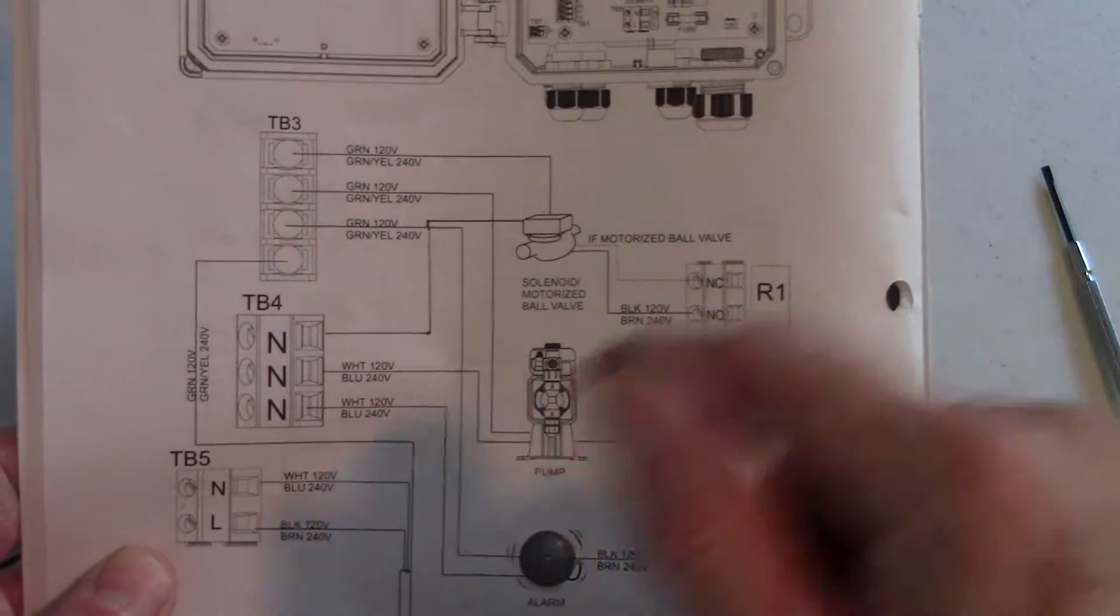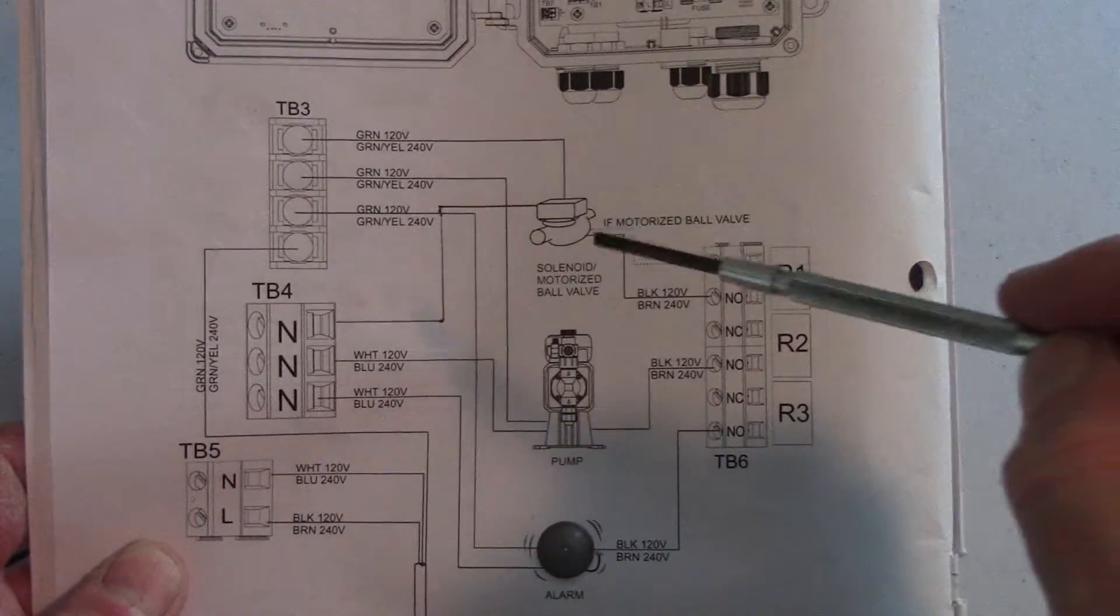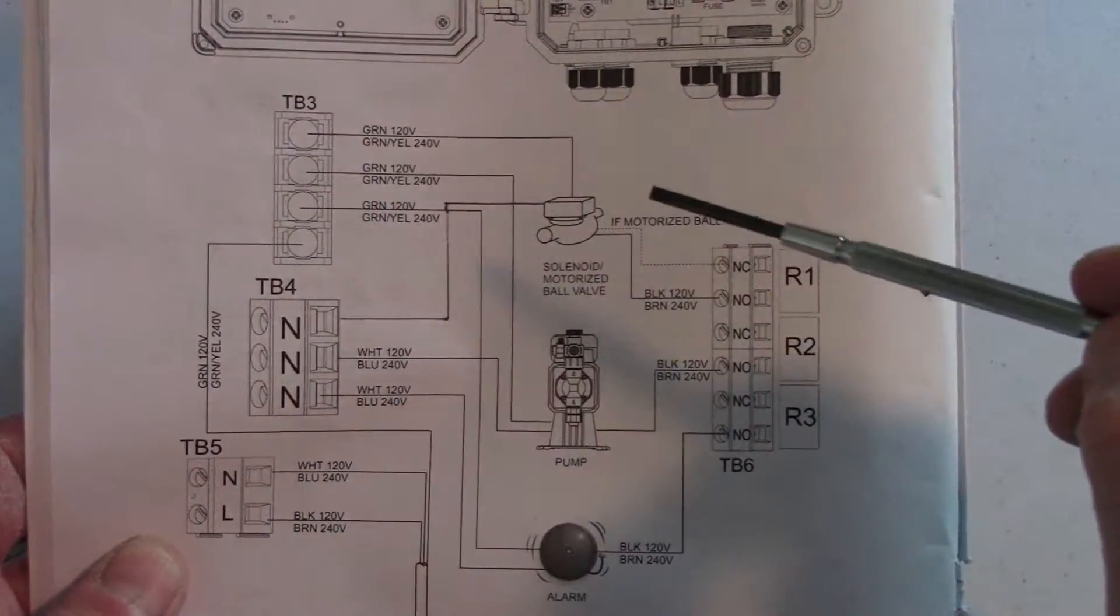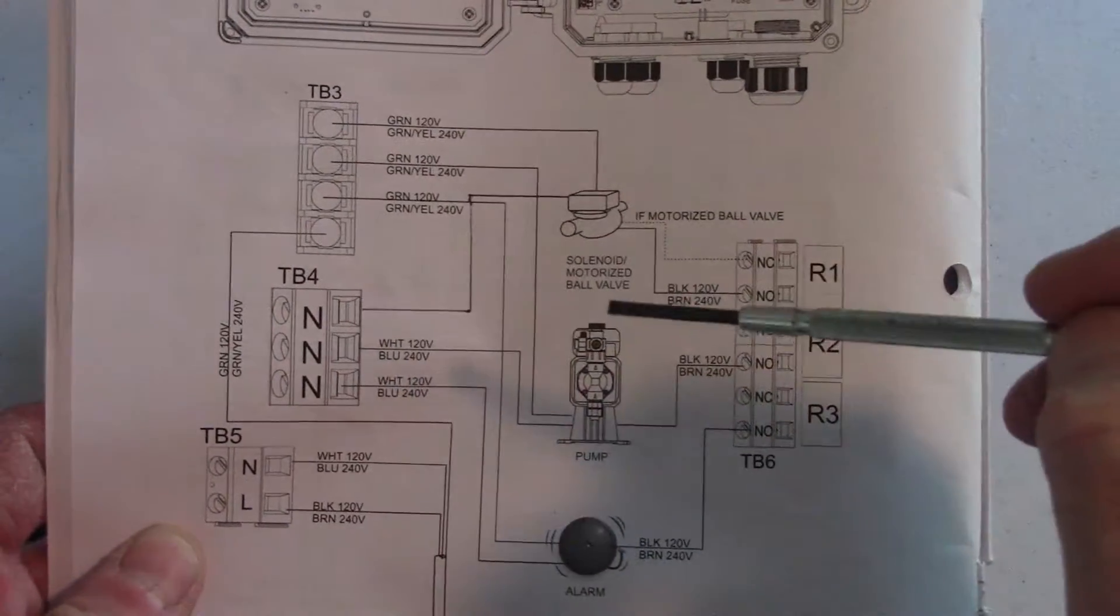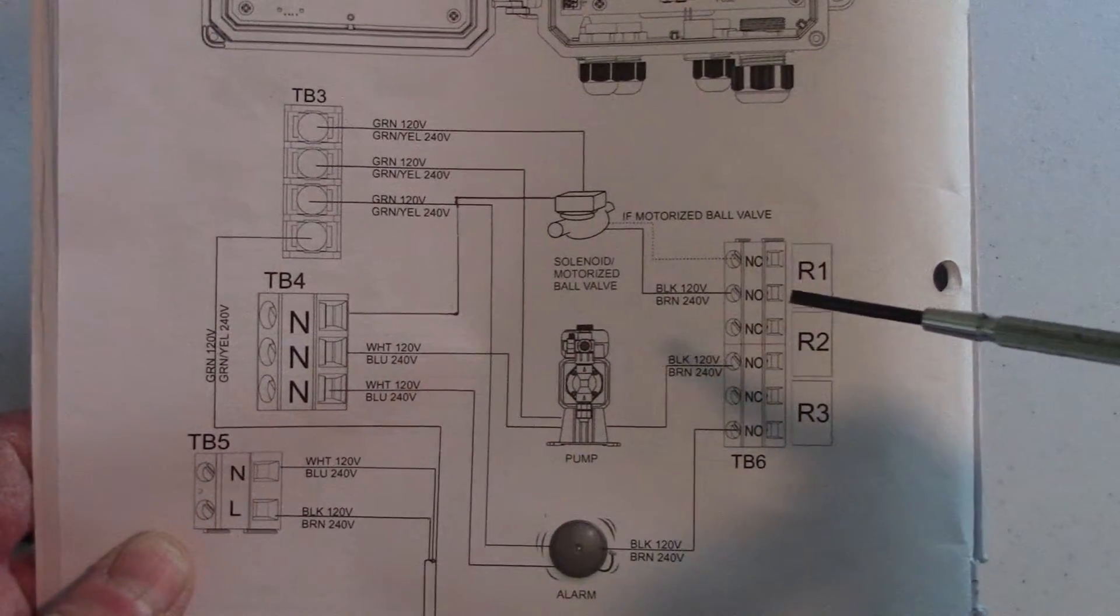Polarity is not critical for the solenoid valve so if you look at the wiring diagram for the controller you'll see the ground goes to TB3 and the other two wires go to TB4 and then R1 on the normally open side.